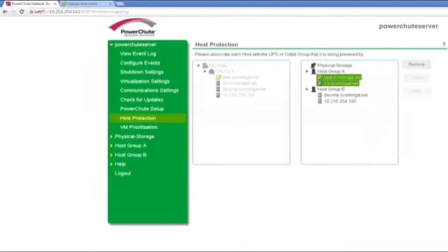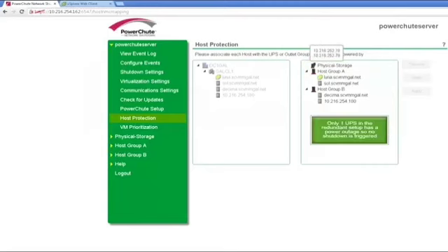We trigger a power outage on the UPSs connected to one of the mains power supplies. This will affect the UPSs in host group A and one of the UPSs powering the storage array and PowerChute machine. Only one UPS in the redundant configuration protecting the physical machine and storage array is on battery. Therefore, no shutdown sequence is triggered for this equipment.